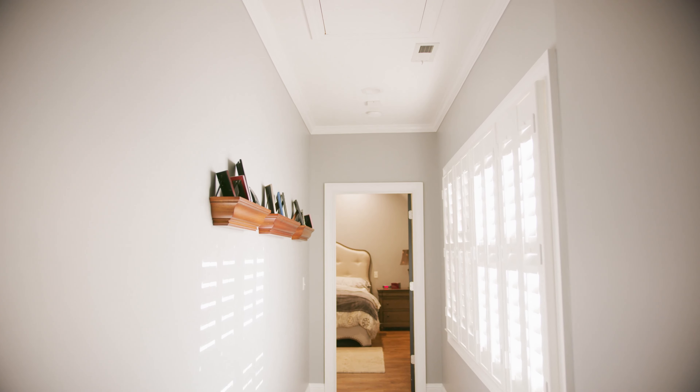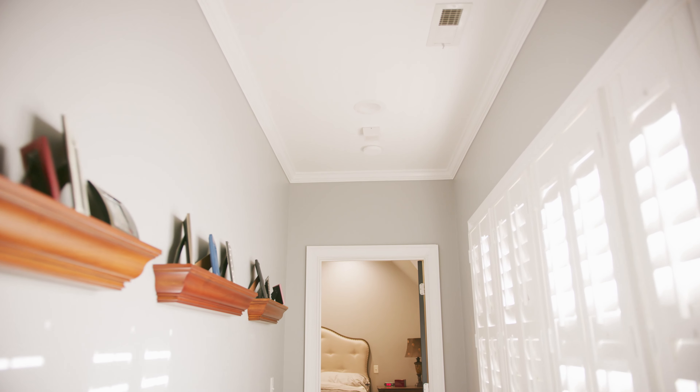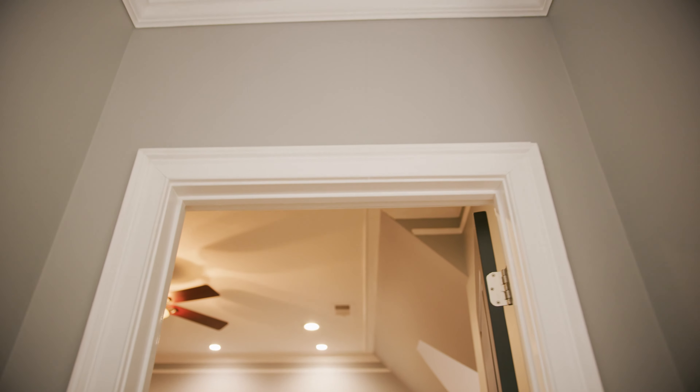Your floor is probably pretty flat, which is a simple shape, but the top floor ceiling is not so simple. Ever felt hot in a top floor room in summer even though the lower floors are nice and cool? Chances are it has nothing to do with air conditioning — it's because of holes in the skin of the house over your head. Take a walk around the top floor and keep your eye out for places where the ceiling height changes from room to room. Wherever this happens there's probably air leakage and insulation issues. Any ducts that plug into the ceiling are even more likely to leak air, since the ductwork is now at the highest point in the home.